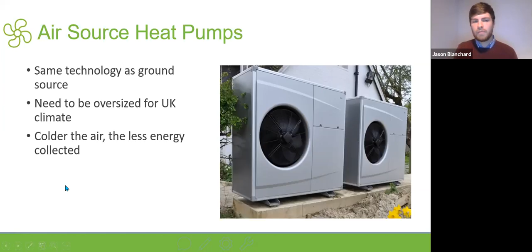Just to outline that clearly: a ground source heat pump's COP, which stands for coefficient of performance - your heat pump efficiency - will be looking at around 4 units of heat out. So 3 from your heat source or the environment, and 1 from electricity. An air source heat pump, we're looking at around 3 to 1 around the year - that's 1 unit of electricity for every 3 units out.